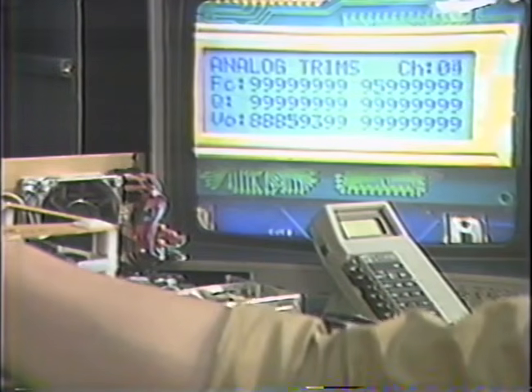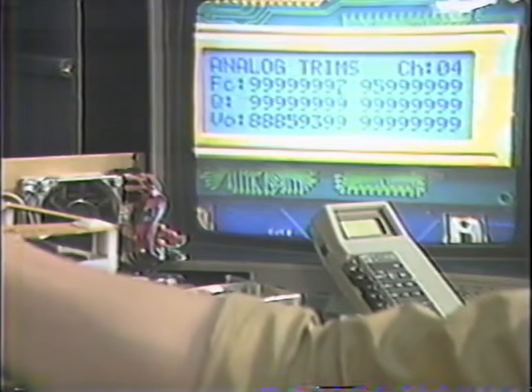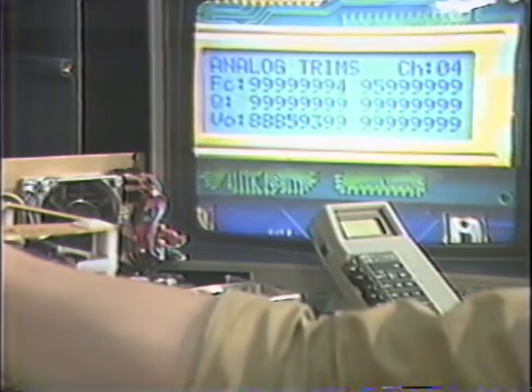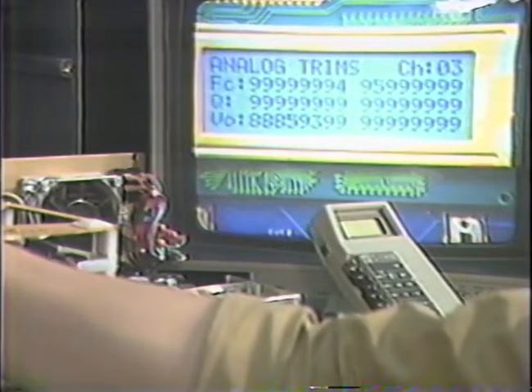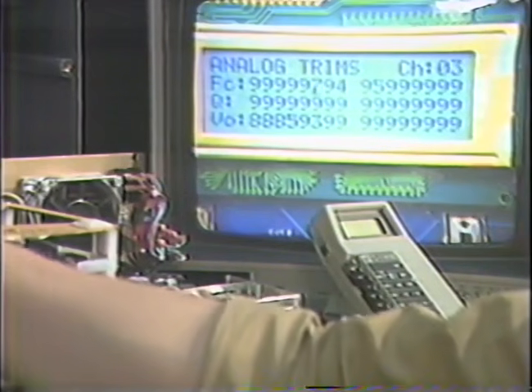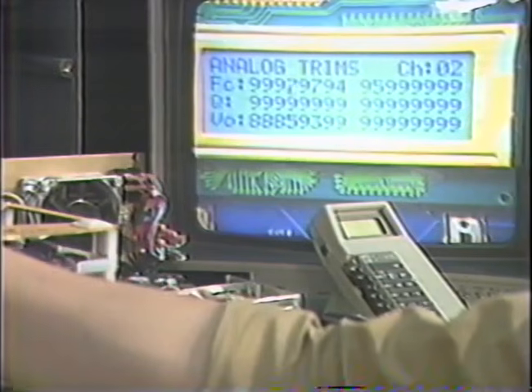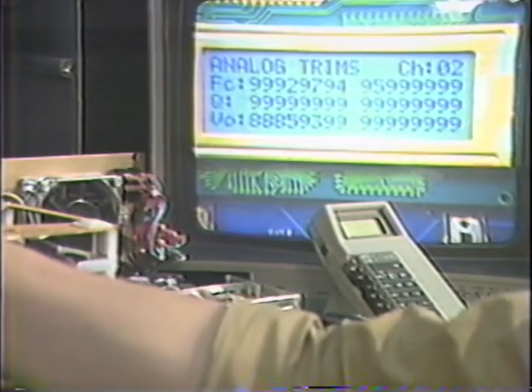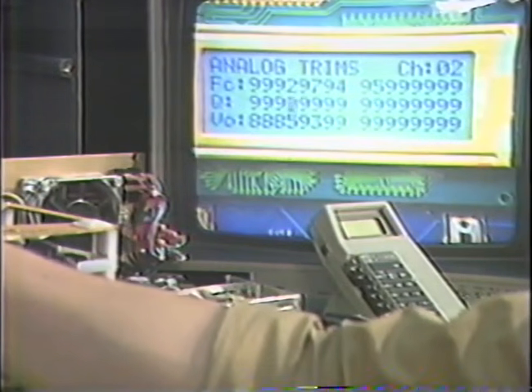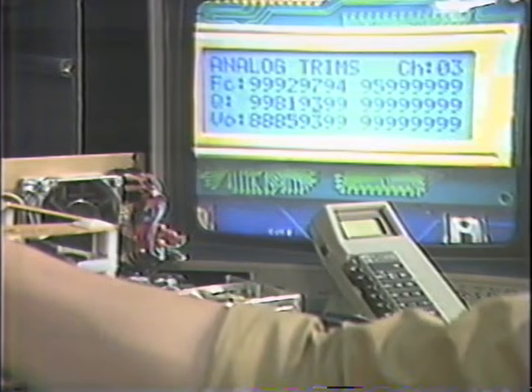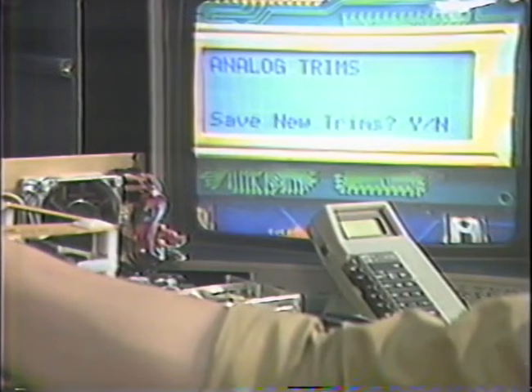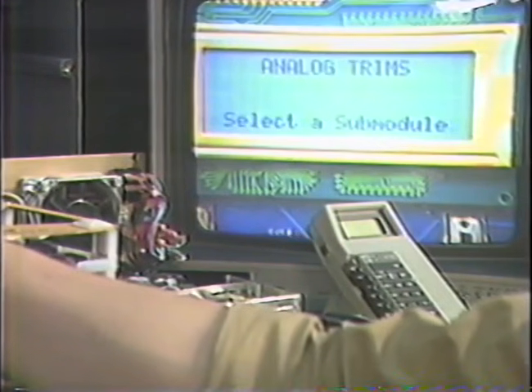Select each of the other channels and bring down their FC value until they oscillate at approximately the same pitch as the reference channel. This is a good rough setting of the FC balance between channels. Next, go to the Q line and lower the values until each channel just drops out of oscillation. This will be a good rough trim of the relative balance of Q between channels. Hit the Enter button and press the Yes button to save these trims. Press the Master button to exit the module.